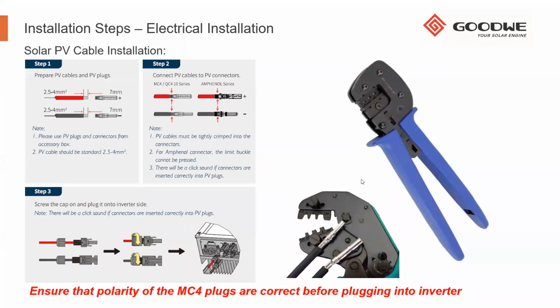Same for our PV cables. Generally, I think our standard now is MC4, so you'll always find the MC4 connectors. It's also always advisable to use a proper crimping tool to make sure that there are no loose connections or hot connections. I've seen this too many times in the past where we don't use a proper crimping tool, and that can end up melting the whole terminal, and it's just not a good sight to see.